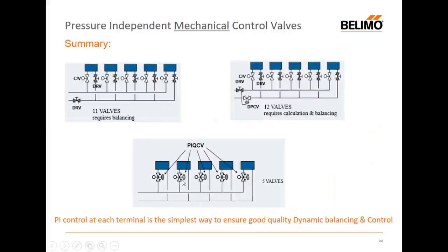Our valve authority is going to be close to one. We don't need manual balancing valves. We may elect to have a measuring device if we don't feel comfortable with this arrangement, but not really being able to measure the flow too well directly. We can, by delta P calculation, determine the flow, but you can see straight away, we've simplified the installation and we only have five valves. So this is a real benefit to the installer, because he has far less commissioning to do, and it could be that the supplier or the manufacturer is going to pre-configure these valves so that they arrive on site preset. And then as long as they're labeled appropriately, they can be installed and they're good to go from the off. So PI control, much simpler, much easier to understand, and simplifies the installation and reduces the cost.